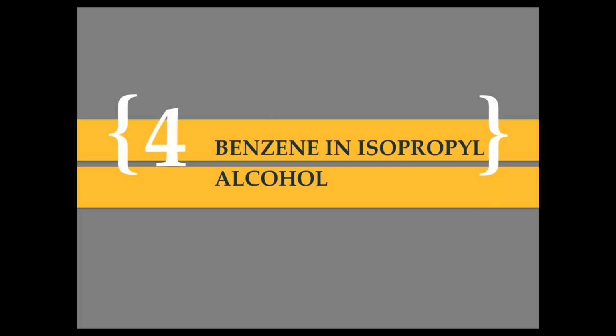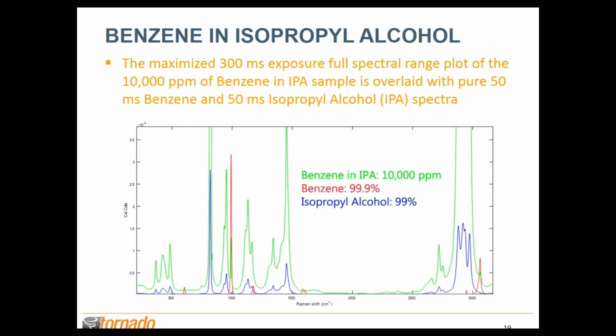Here below is a spectral plot of the maximized 300 millisecond exposure of the highest concentration, 10,000 ppm of benzene in IPA, which is overlaid with the pure 50 millisecond benzene and the 50 millisecond exposure of IPA. And like I said, I use this often as an informative tool to help me decide what peak to optimize the exposure on, as well as the PLS calibration.